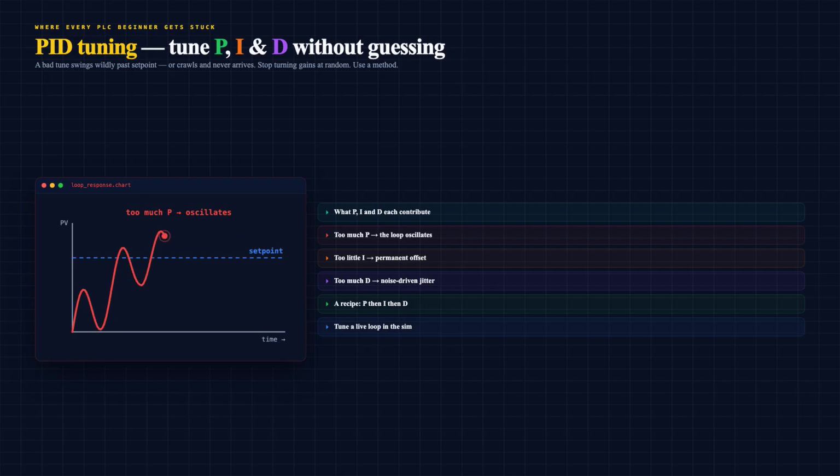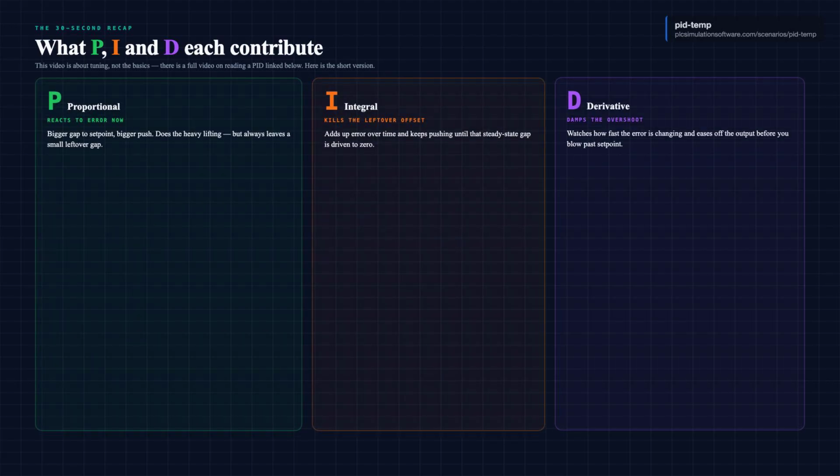Quick recap. This video is about tuning, not the basics. If you want to know what a PID even is, there is a full video on reading a PID linked below. Here is the 30-second version. P, the proportional gain, reacts to the error right now. The bigger the gap to set point, the bigger the push. P does the heavy lifting, but on its own, it always leaves a small leftover gap.